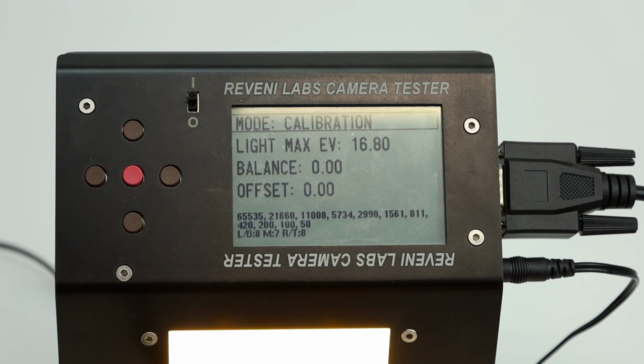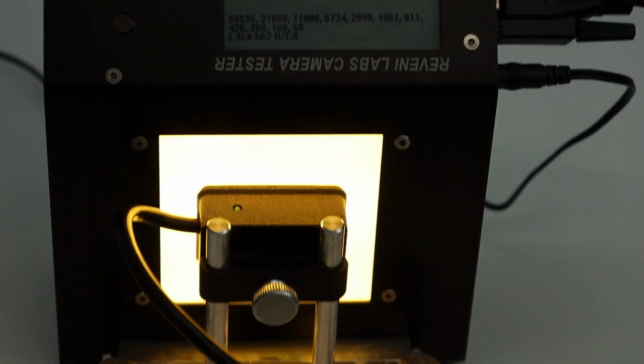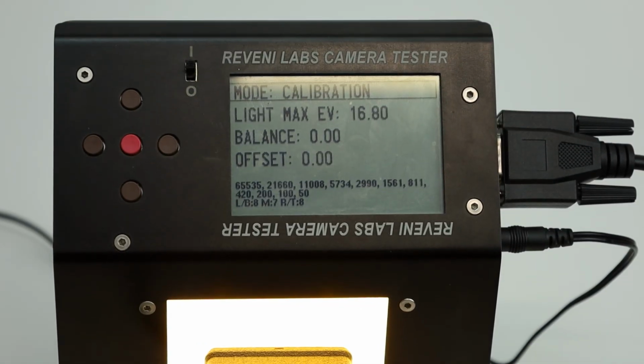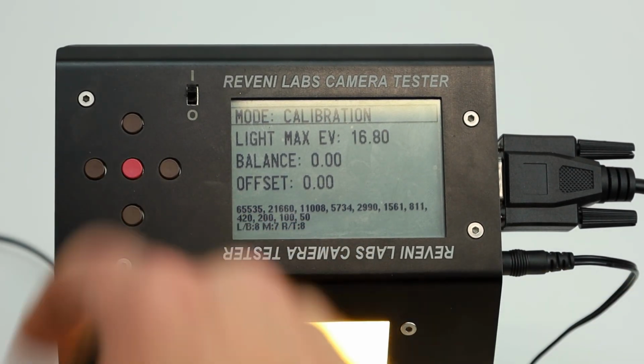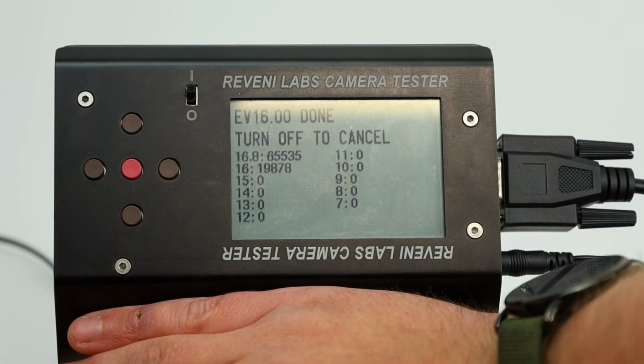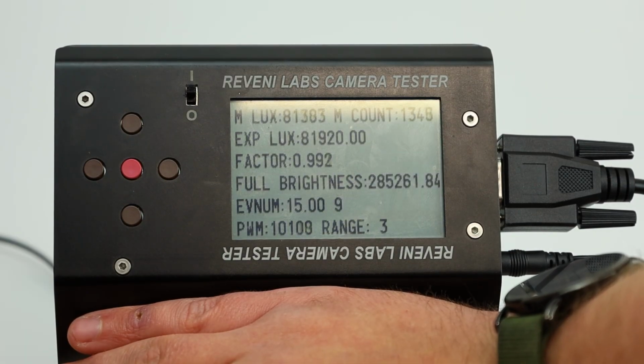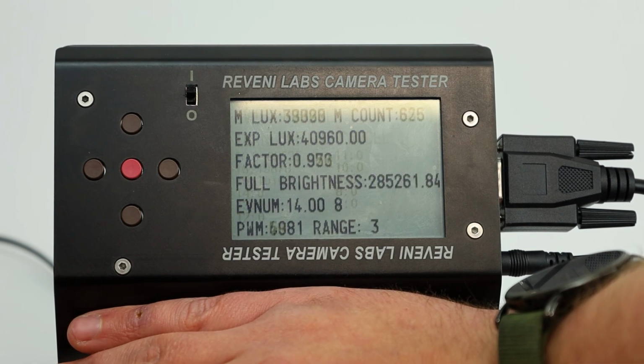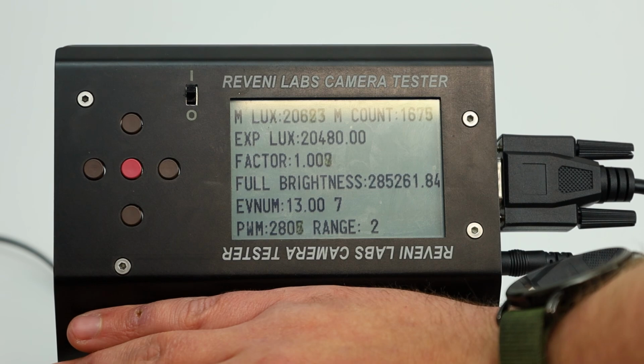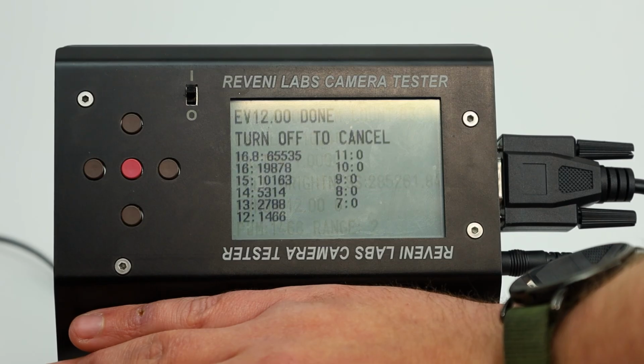First step is to run the regular calibration procedure. So place the sensor head at the light source, and then enter the menu, go to the calibration page, and click the center button. If you're calibrating in a high brightness environment and you don't have the fabric shade on the front of the tester, you should shield the room light with your hand just to minimize any error in the calibration, particularly when it checks the low brightness EV levels.